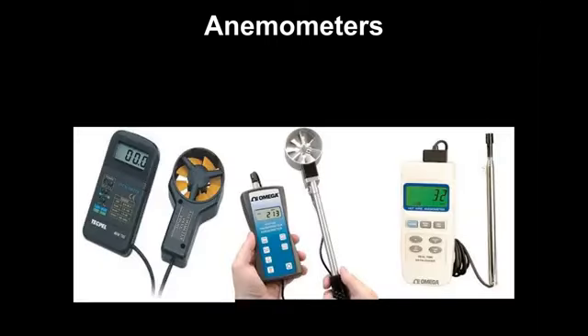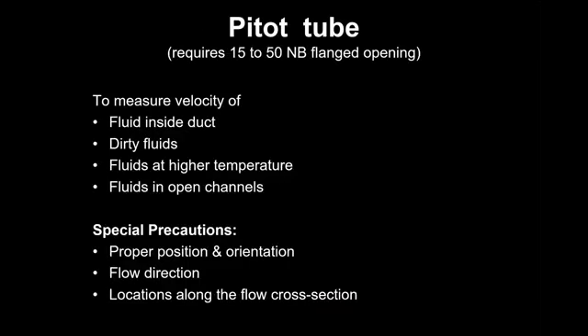These are the anemometers. Again, it is from the internet. This is the hot wire anemometer. These are vane type anemometers. Another instrument that is used is a pitot tube. Pitot tube has an SS probe, so it can be used for higher temperature. It can be of any length. We have used a pitot tube of 3-meter length also. So it is not an issue to measure a high diameter duct. We can do that.